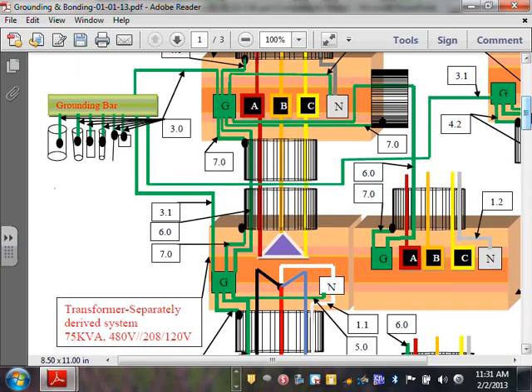Now we'll talk about this. You don't have to. You're absolutely right. But I want to emphasize, now you create a new neutral, you bond the neutral to the ground bar, and you have to ground the ground bar of the transformer to the grounding electrode system inside your building. You have two options. Option number one is to take that conductor all the way to the ground bar if it's in close proximity.